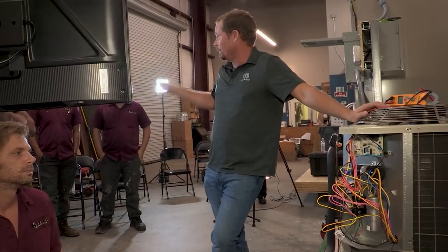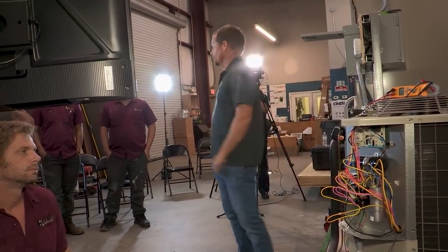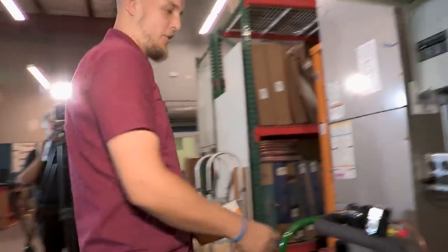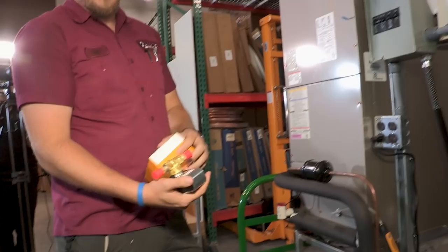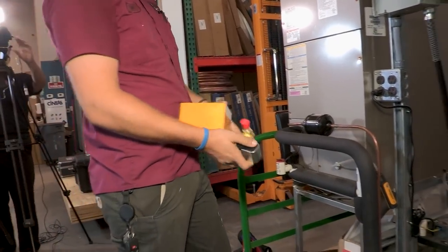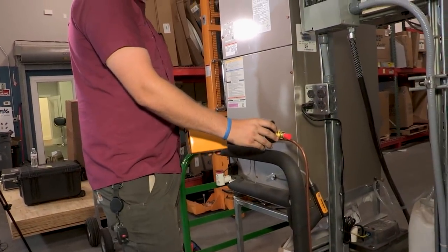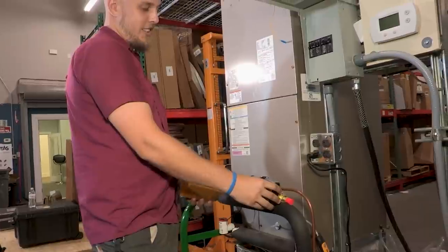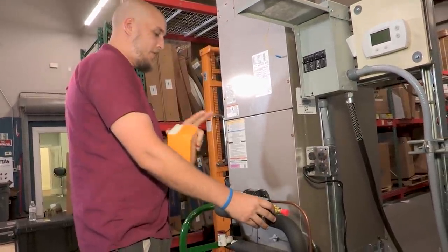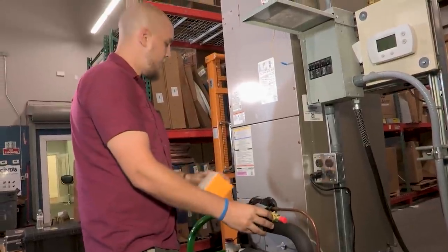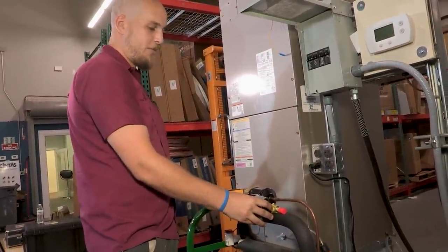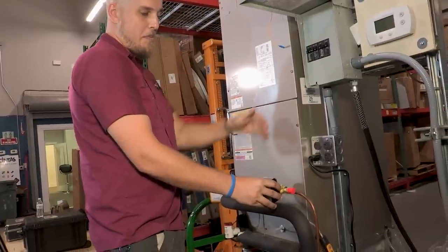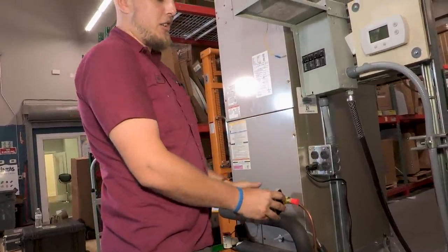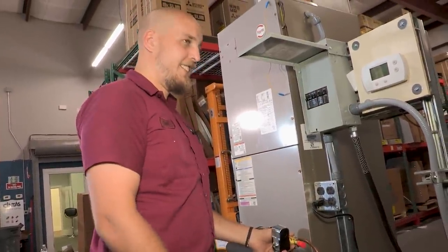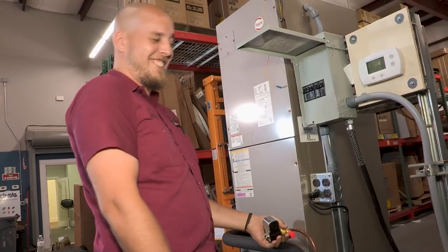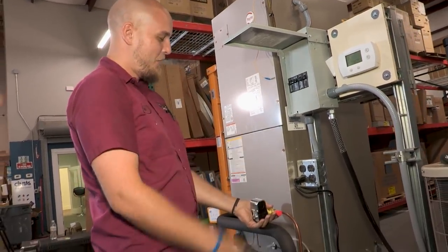Cool. All right, so Sam, I want you to talk through this liquid line solenoid that I handed you. So we have our solenoid here. It's called the liquid line solenoid because it is installed in the liquid line. How does it work? It's basically designed to close on no call for cooling, which will prevent back liquid coming to our condensing unit. Hence the liquid line shutoff valve.